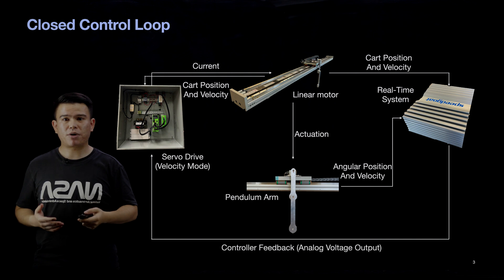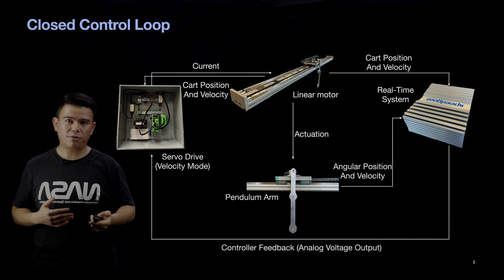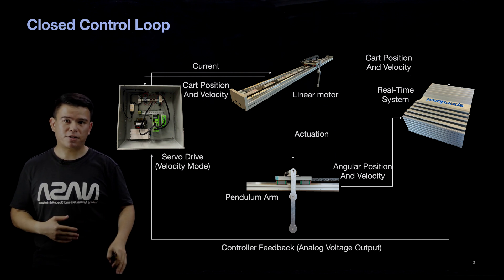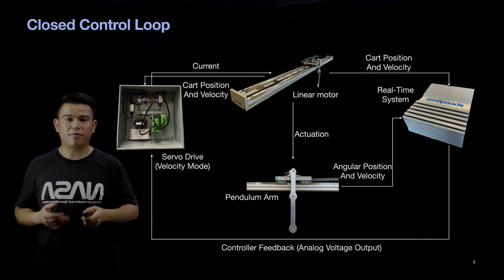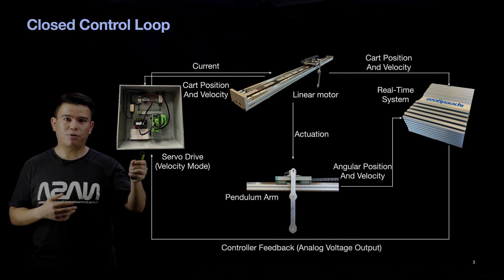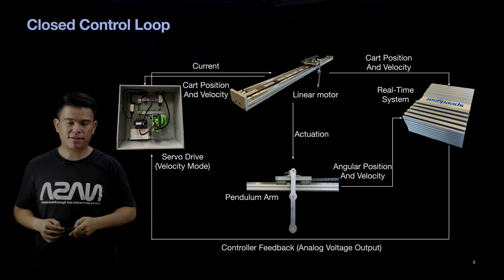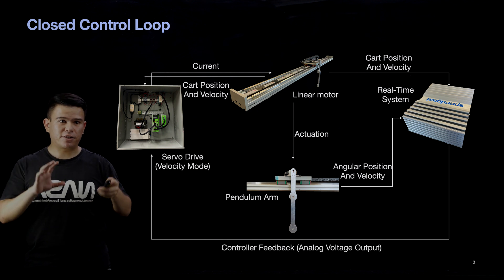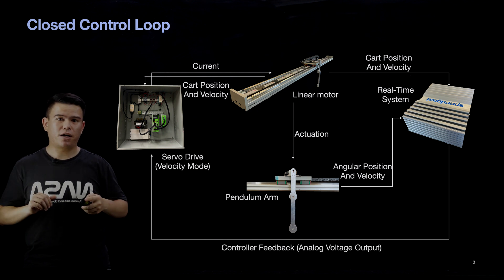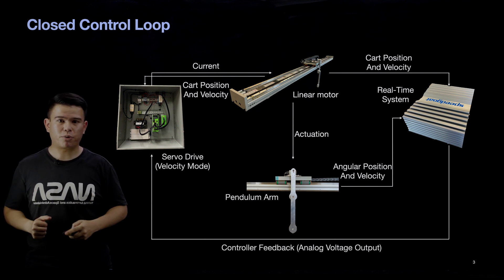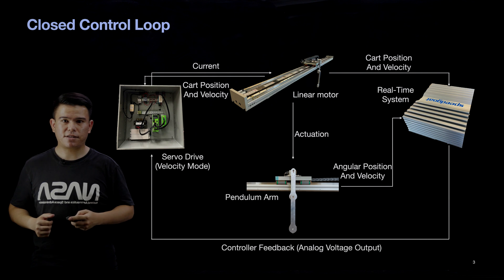It then sends that desired speed information using an analog signal to the servo drive. The servo drive compares the current speed of the linear motor with the desired speed to determine whether to increase or decrease its velocity. That's the entire control diagram we're using in the system.